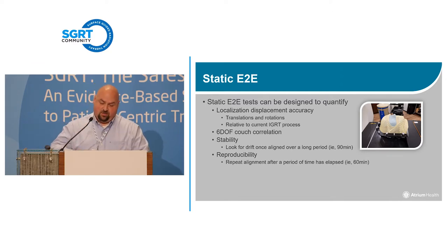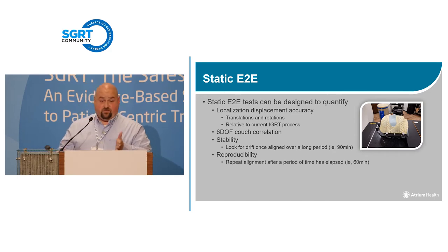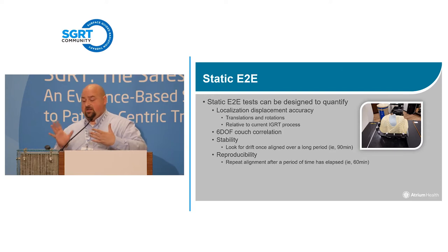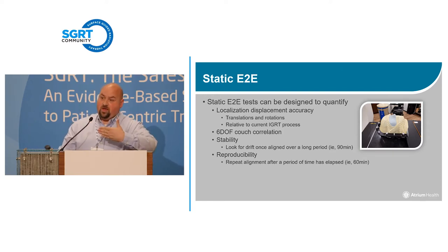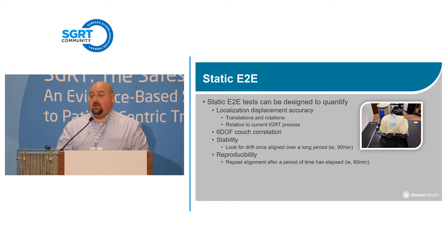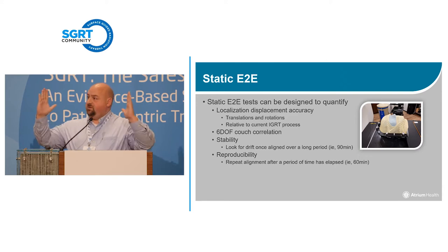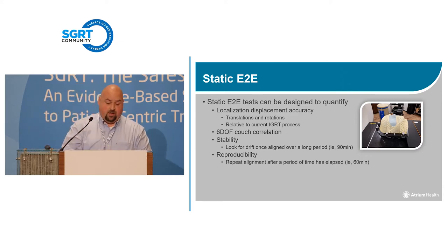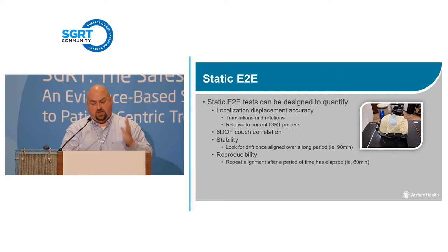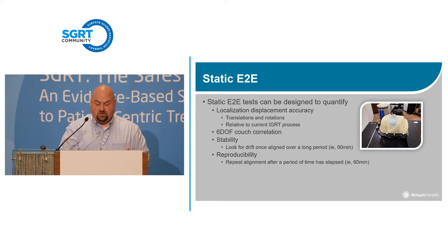For static testing we used the Max HD head phantom and a compass mask — we treated it exactly like a patient. We don't have advanced calibration right now, so we do see a little walk. That showed us our SRS cases have a 1.1 mm walk. That's a known issue and we could only correlate that because we had an end-to-end test. You can test position stability, look at drift, keep cameras on for an hour, and see what happens — all satisfying many TG-147 recommendations.